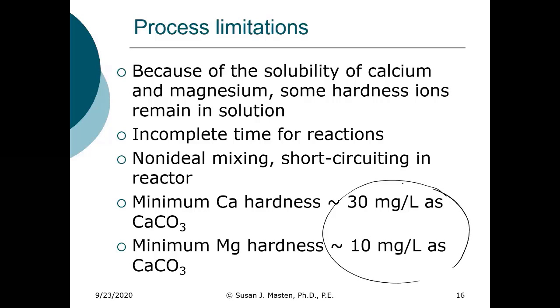The other thing is that solubility reactions are not rapid. It's unlike an acid-base reaction, which is almost instantaneous. Solubility reactions are time dependent, and there may be incomplete time for a complete reaction to occur within the flocculation basin. There's also non-ideal mixing. We've talked about that. We've talked about short-circuiting. I mentioned that, and that can result in process limitations.